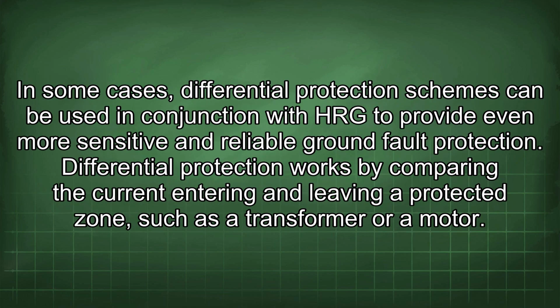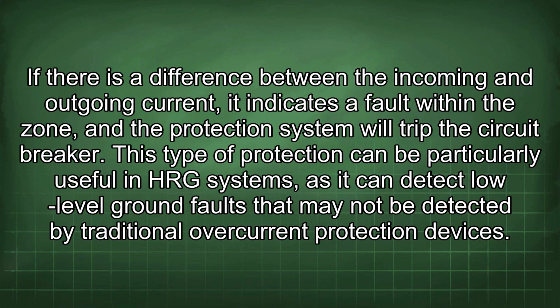In some cases, differential protection schemes can be used in conjunction with HRG to provide even more sensitive and reliable ground fault protection. Differential protection works by comparing the current entering and leaving a protected zone, such as a transformer or a motor. If there is a difference between the incoming and outgoing current, it indicates a fault within the zone, and the protection system will trip the circuit breaker. This type of protection can be particularly useful in HRG systems, as it can detect low-level ground faults that may not be detected by traditional overcurrent protection devices.